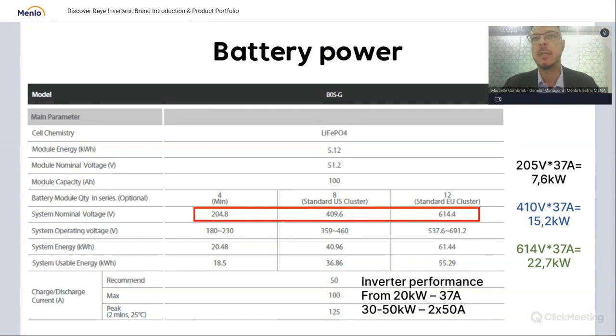Looking at the battery power output, if we take the basic 20 kilowatt, so 20 kilowatt, 37 amps, and if we look at the nominal voltage of 4 batteries, 8 batteries, and 12 batteries, so if we start with 4 batteries, we get a power output of 7.6 kilowatt. If we look at 8 batteries, which is 409.6 volts, that gives us 15.2 kilowatt. And if we look at 12 batteries, which is 614.4 volts, that gives us 22.7 kilowatt. Also, just to remember, from the 30 kilowatt upwards, you can multiply the batteries by 2. So it will increase your battery capacity. Next slide, please.